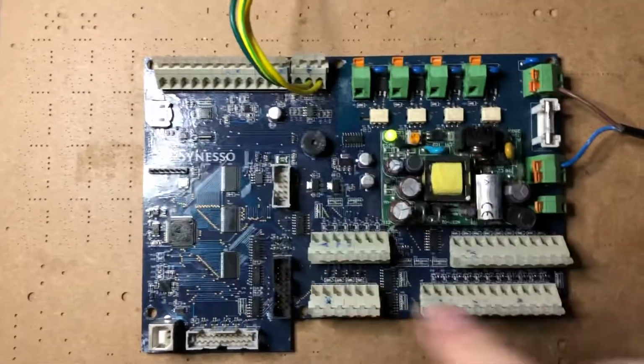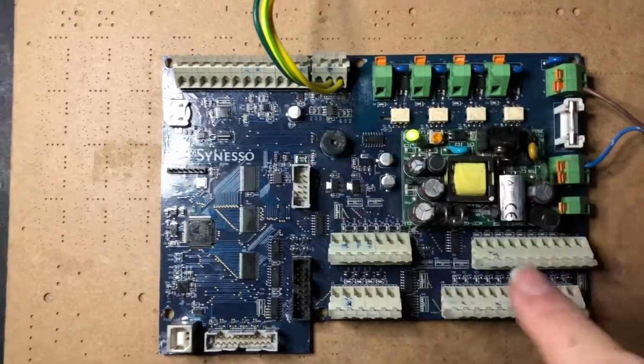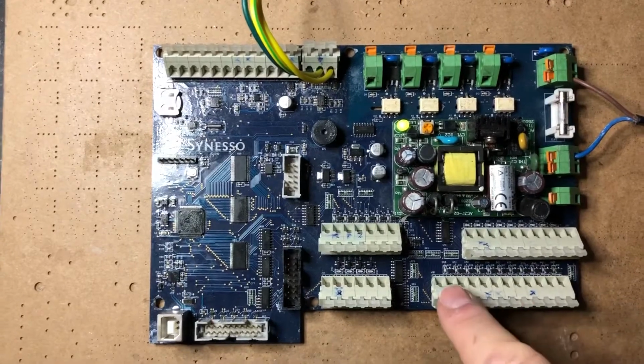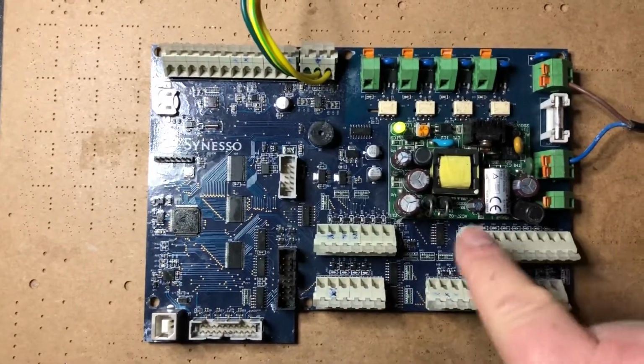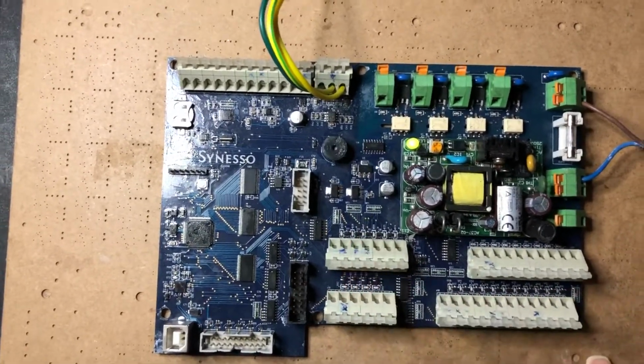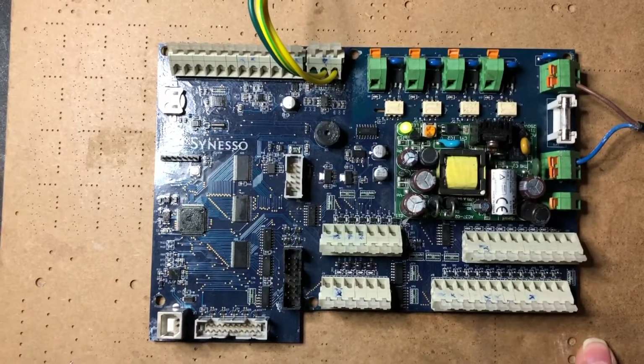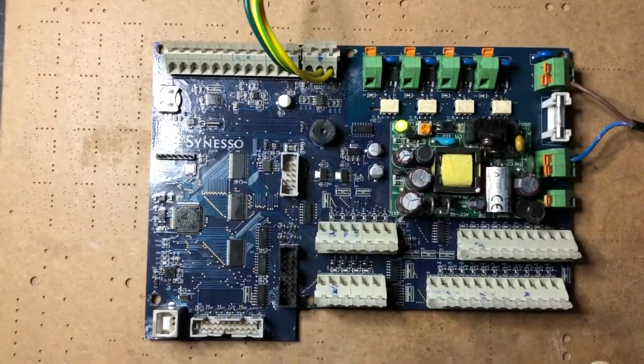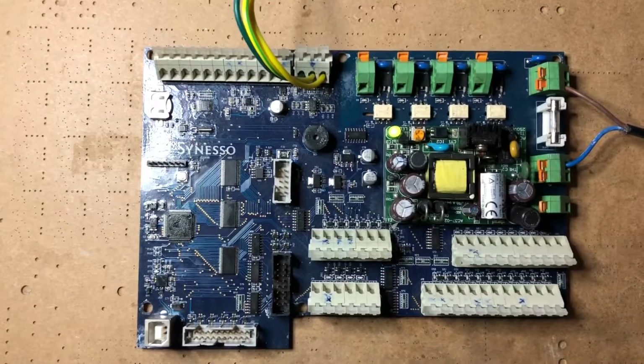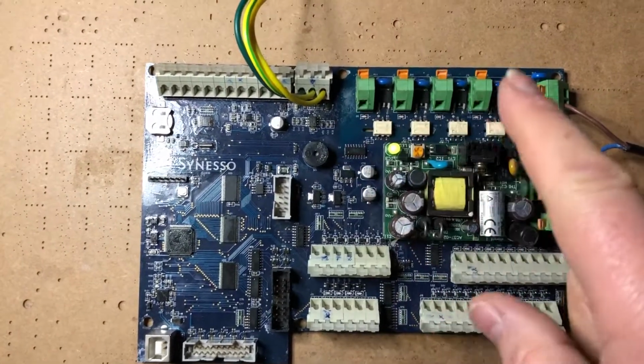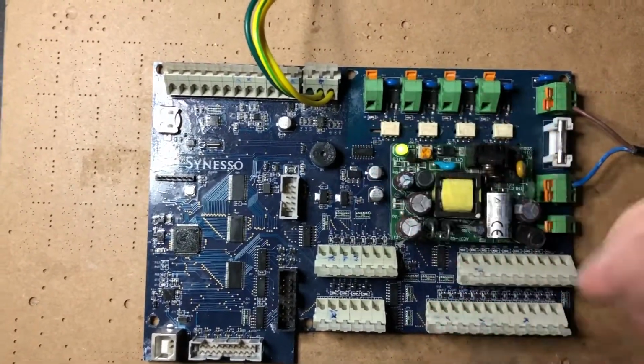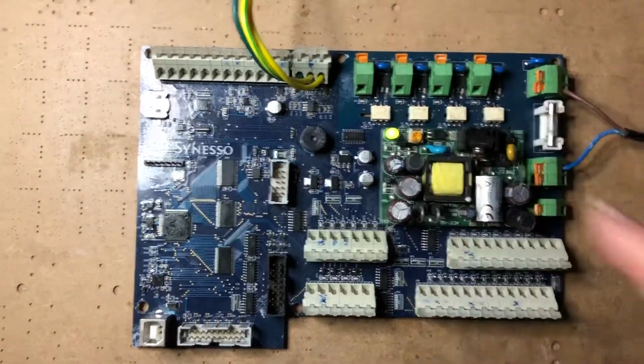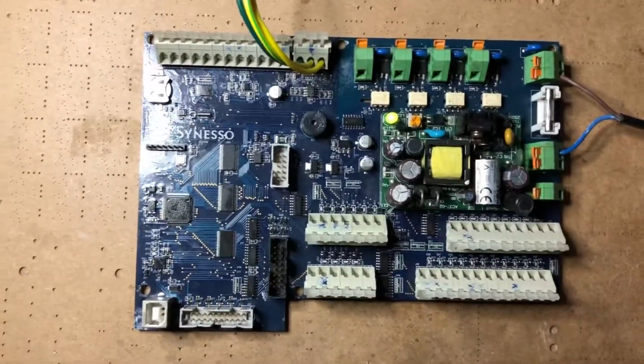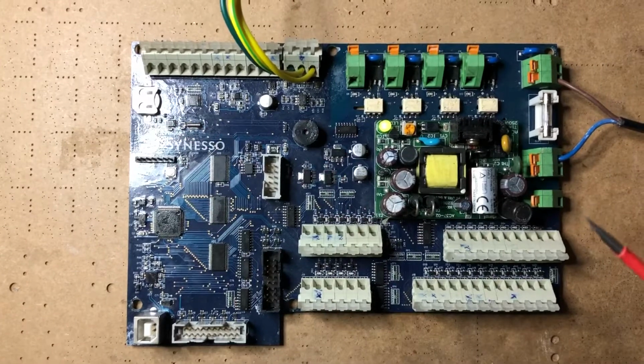So change all your inputs to match your new outputs. You'll have to move your solenoid valves across, move your inputs, your lever switches, your flow sensor, and your heating element to match whatever groups you've decided to use, whether it be 1, 2, and 4, or 1, 3, and 4, or whatever you choose to do, 2, 3, and 4. Whatever you choose to do, make sure your inputs match your outputs.